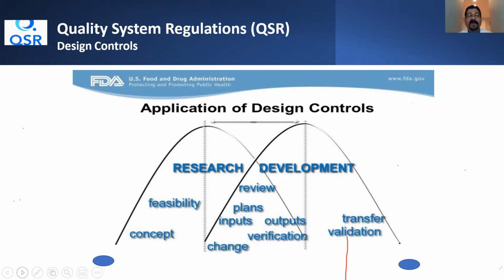Then you have to make a plan. When you make a plan, you have to think about the design inputs, and you have to see that these design inputs result in design outputs. And then you have to verify the design of the product. If any change happens, again you review, you change your requirements, you see whether it is changing your design outputs or not. Now, when you come to the development part, once you complete this research work and your device is ready, then you are transferring it for validation or manufacturing. That part comes under development.